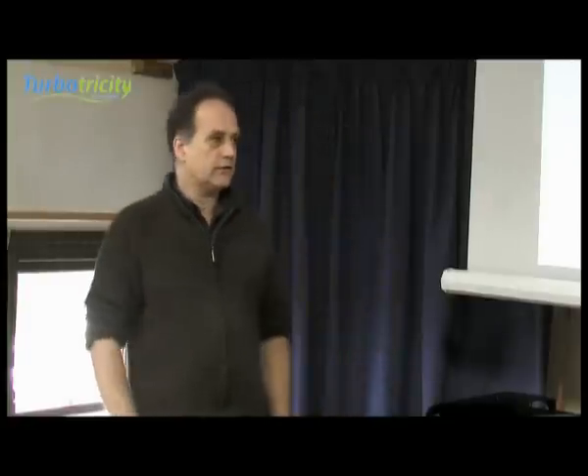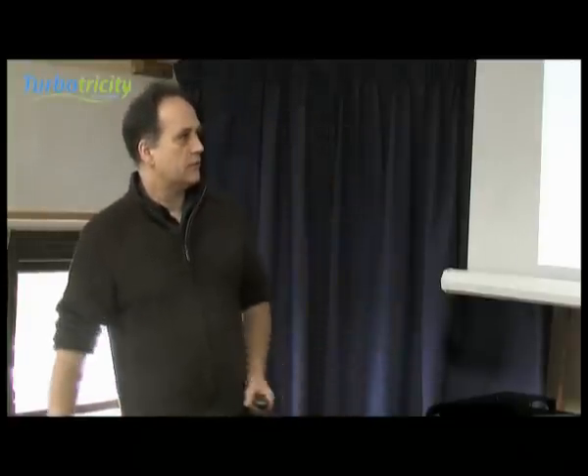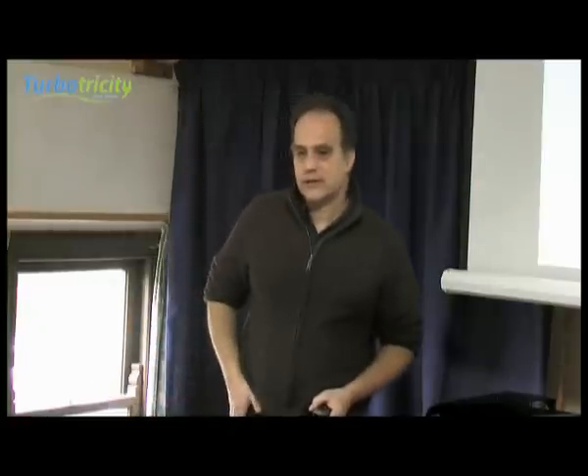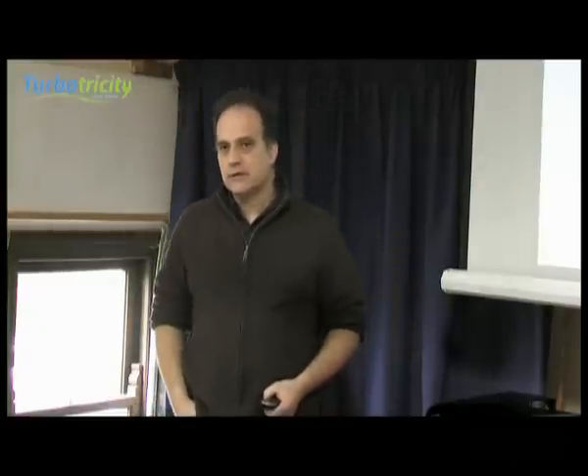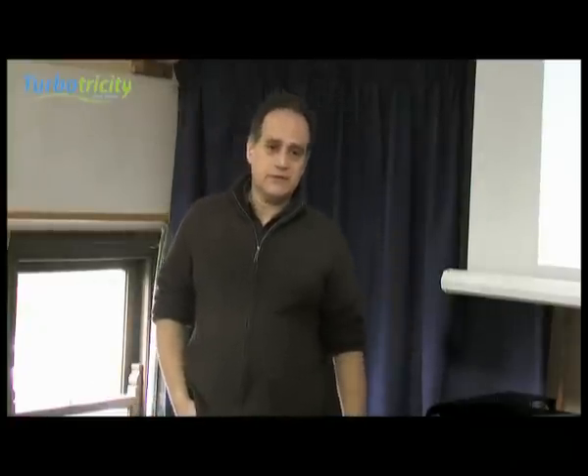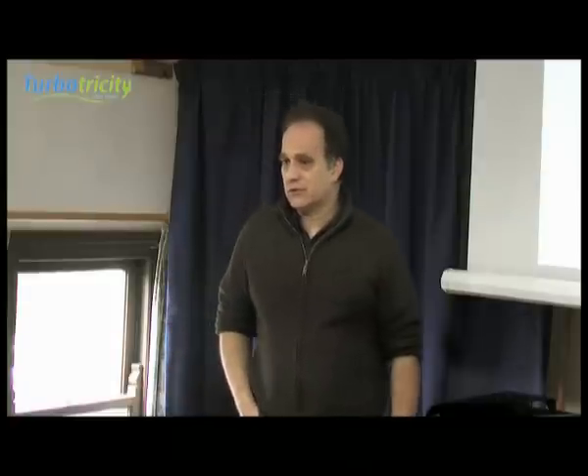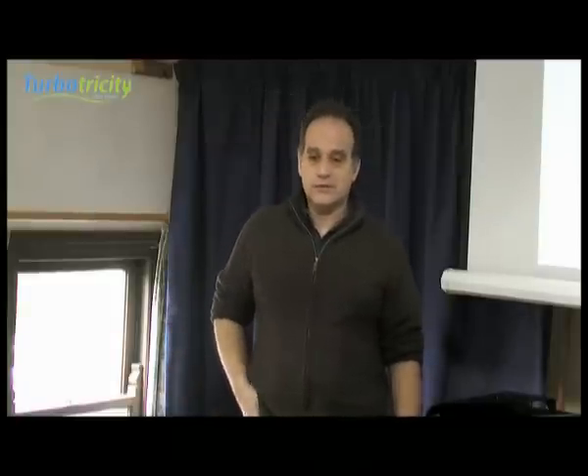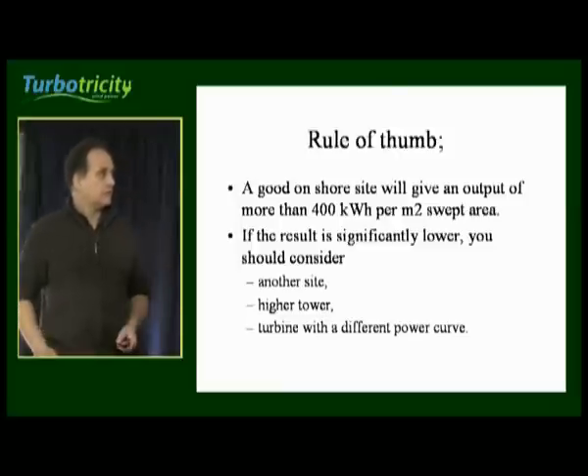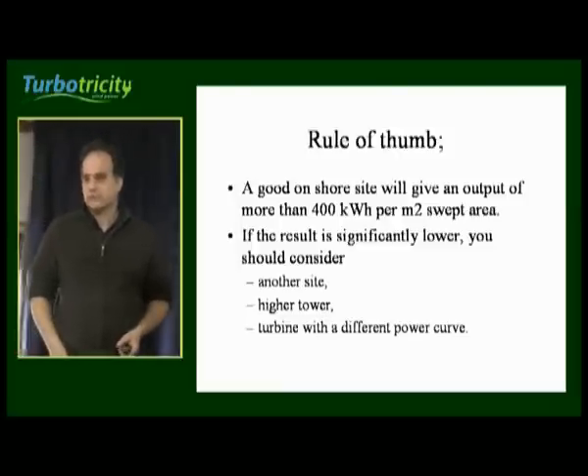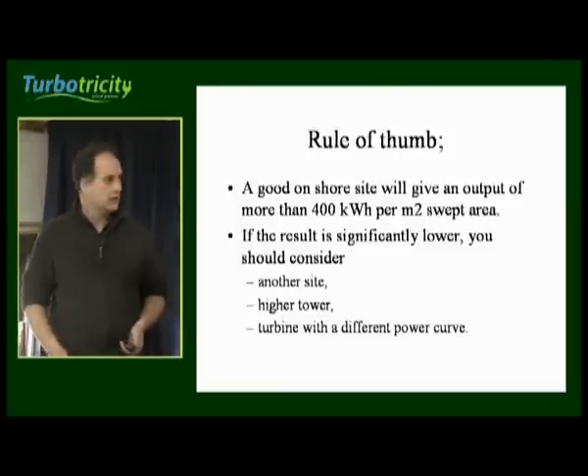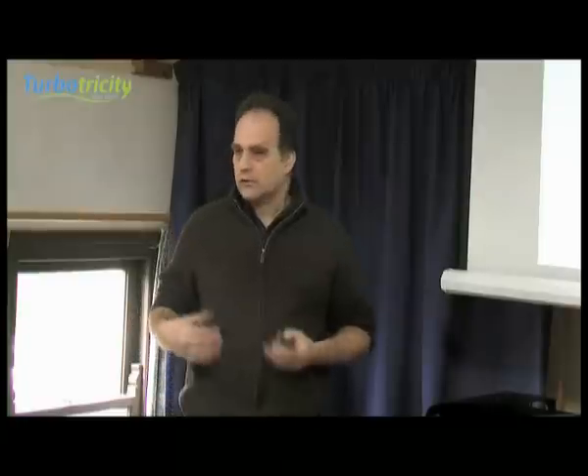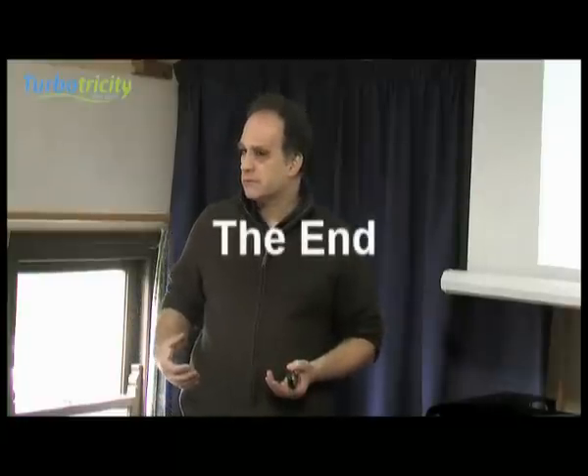Having done all that, if you arrive at a situation where your output is below 400 kilowatt hours per square metre of swept area, you can do the finances and work out whether the turbine is a viable proposition. But the rule of thumb is that if it's working out at less than 400 kilowatt hours per square metre, they suggest you should either look at another site for your turbine, a higher tower, or look for a turbine with a different power curve.